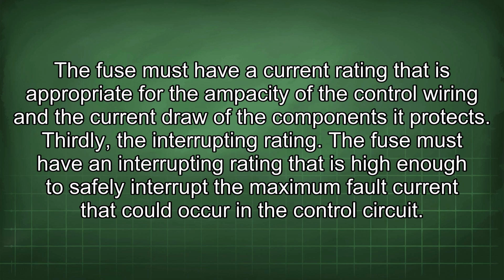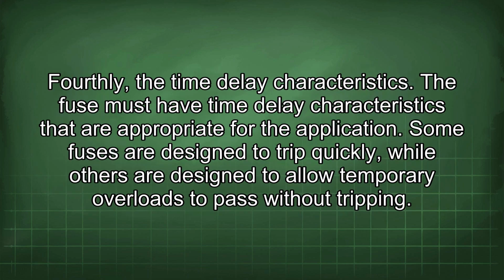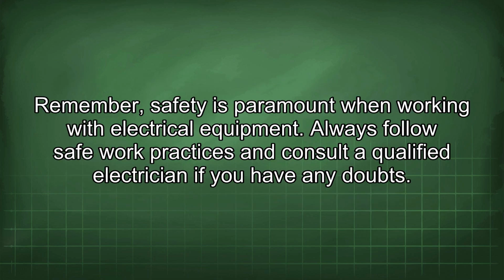Thirdly, the interrupting rating. The fuse must have an interrupting rating that is high enough to safely interrupt the maximum fault current that could occur in the control circuit. Fourthly, the time delay characteristics. The fuse must have time delay characteristics that are appropriate for the application. Some fuses are designed to trip quickly, while others are designed to allow temporary overloads to pass without tripping. Remember, safety is paramount when working with electrical equipment. Always follow safe work practices and consult a qualified electrician if you have any doubts.